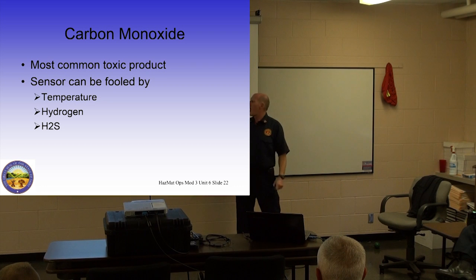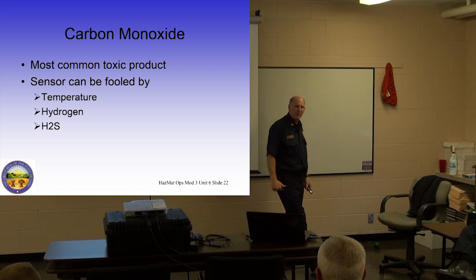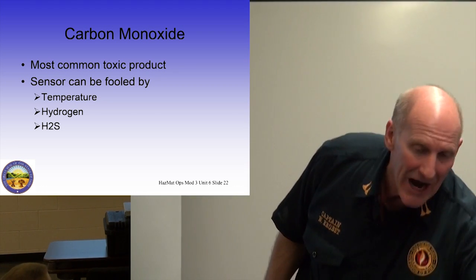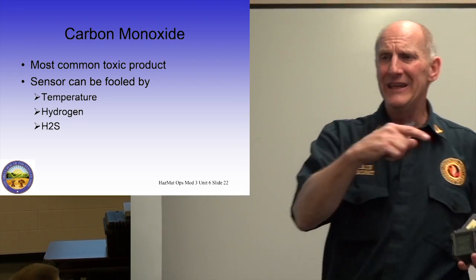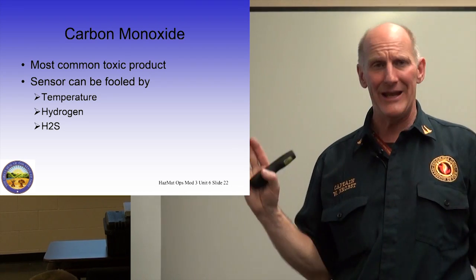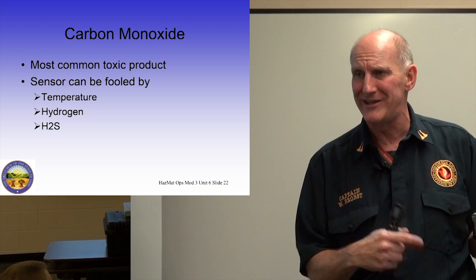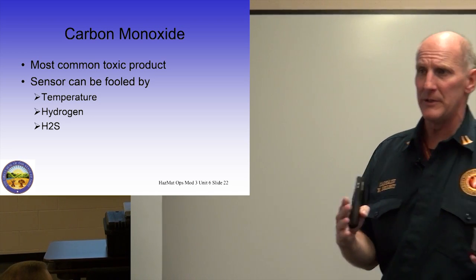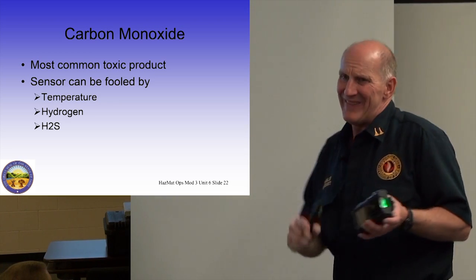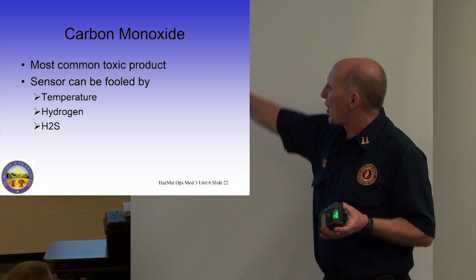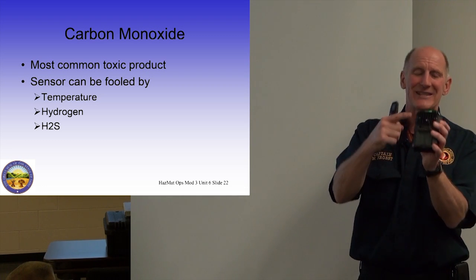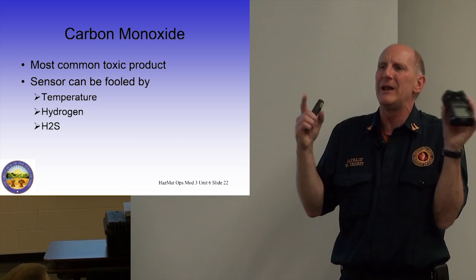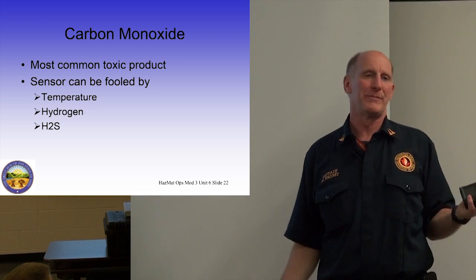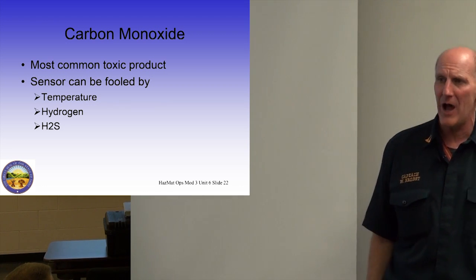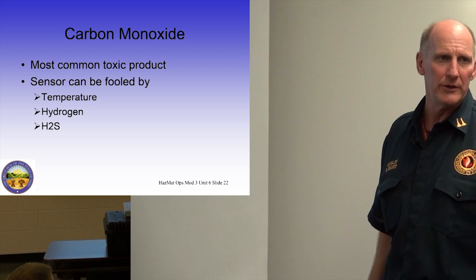One of the most common things that will fool the carbon monoxide sensor is hydrogen gas. If they've got a lead acid battery being charged downstairs in the basement next to the sump pump, that charging battery can produce hydrogen gas and it will fool the meter, giving you readings of carbon monoxide. It's not carbon monoxide, it's just fooling you.